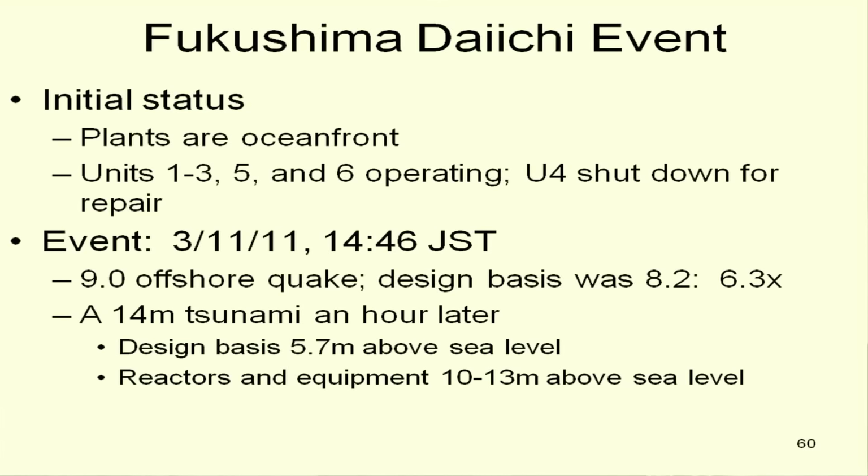The event on March 11, mid-afternoon Japan time, they had a 9.0 offshore quake, some say 9.3, whatever. It's in that ballpark. Design basis was an 8.2, but because this is a logarithmic scale, that's about a 6x difference. It's not as trivial as it looks comparing 8.2 to 9. And then roughly an hour later, a 14-meter tsunami came ashore. The design basis was 5.7 meters, and the reactor and equipment were 10 to 13 above sea level.